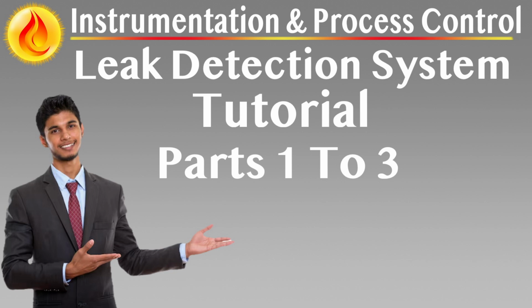Performance benchmarking during commissioning and periodic validation in the field are essential. Operators should conduct blind leak simulations or data-driven testing to verify system response under realistic conditions. Over time, trends in false alarm rates, missed detections or tuning adjustments will reveal the LDS's true capability and reliability.